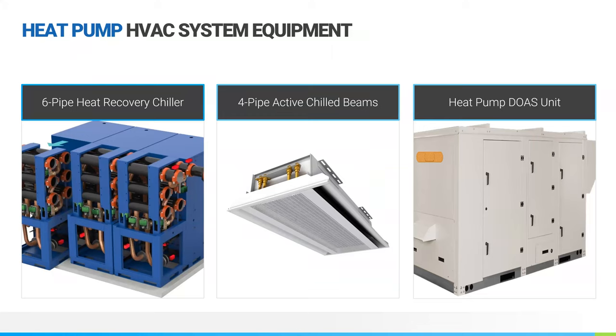Your ventilation air from the unit on the far right there is called an outside air processing unit. The ventilation air, this is big in the COVID world. Your outside ventilation air is pre-processed by that unit, taken through MERV 13 filtration, and then entered into the space at a predetermined rate set by the American Society of Heating, Refrigerating and Air-Conditioning Engineers. So the outside air comes in through that unit and then that air is either cooled or heated using the chilled water, hot water plant that you'll see there on your left.